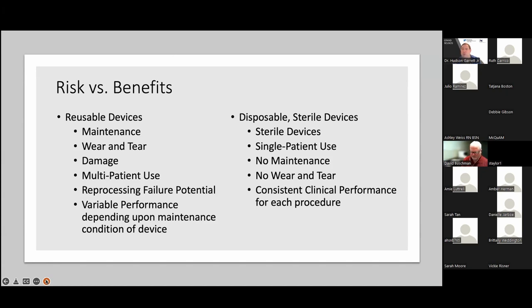If you look at the traditional pathway of reusable devices, you've got to maintain them. There's wear and tear, there's maintenance plans, you may have to send these out and get loaner devices. Certainly, you can't always assess for reprocessing failure. This is not like where you have a load of instruments that goes through sterilization and we get a biological indicator telling us the load was sterilized. We don't have that capability.